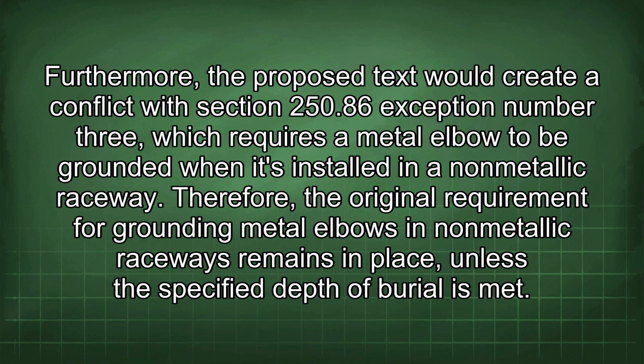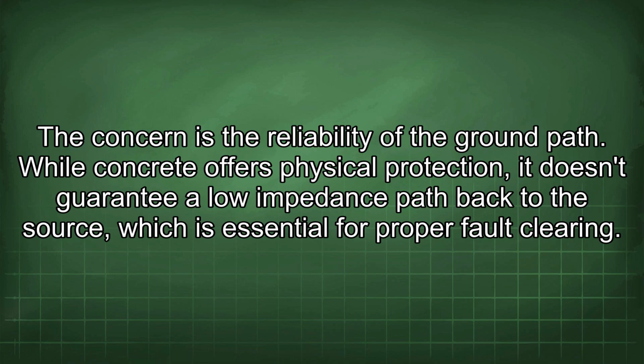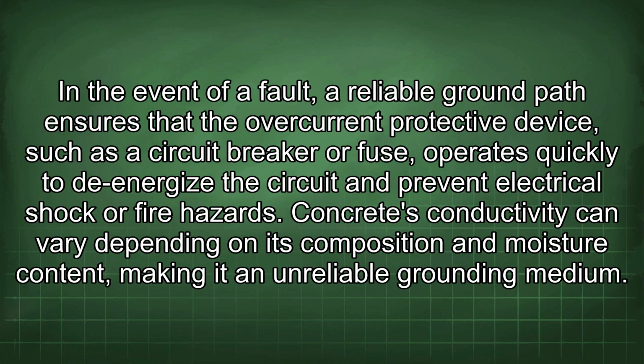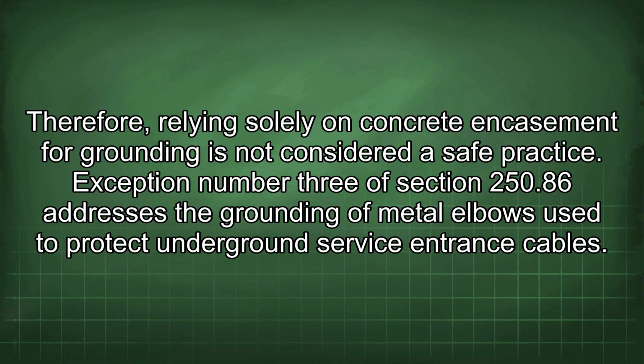Therefore, the original requirement for grounding metal elbows in non-metallic raceways remains in place unless the specified depth of burial is met. The concern is the reliability of the ground path. While concrete offers physical protection, it doesn't guarantee a low impedance path back to the source, which is essential for proper fault clearing. In the event of a fault, a reliable ground path ensures that the overcurrent protective device, such as the circuit breaker or fuse, operates quickly to de-energize the circuit and prevent electrical shock or fire hazards. Concrete's conductivity can vary depending on its composition and moisture content, making it an unreliable grounding medium. Therefore, relying solely on concrete encasement for grounding is not considered a safe practice.